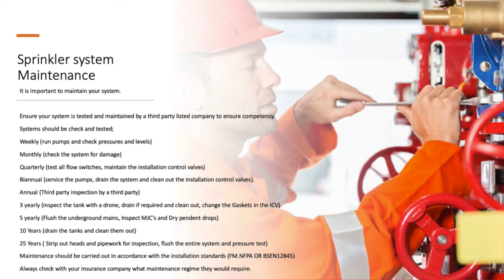Maintenance should be carried out in accordance with the installation standards, so whatever it was installed to, it should be maintained to that FM, NFPA or BSEN 12845. Always check with your insurance company what the maintenance regime is, because they might want more or less - it's down to them. There is a pack coming out on the FPA website, and the insurance will be able to give you it too, which tells you exactly the full list of inspections that have to be carried out on your system. What I've got on the screen here is only a snapshot.